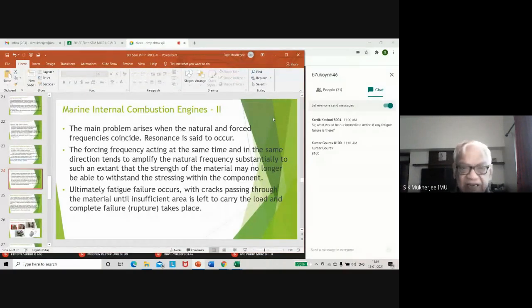We have pump shafts also failing. I could not identify how that pump shaft of a large centrifugal pump simply got cut as if a knife had cut through. You start the pump and you feel, oh, the motor is running, but there is no pressure. What has happened? The shaft from the motor to the pump has got sheared off. Fatigue failure. When we dismantled the shaft, we saw the shaft from the end and we concluded it is fatigue failure. Okay, so let's go through this before I show you the pictures.